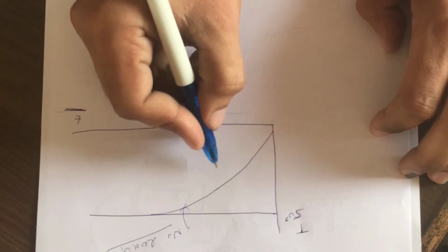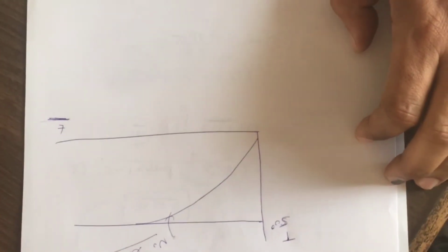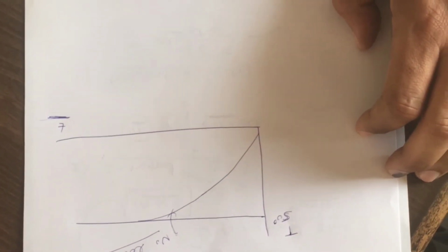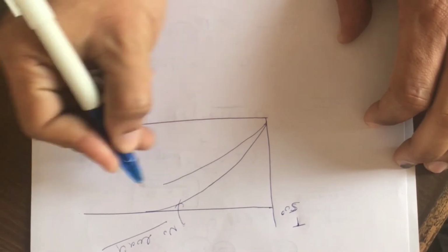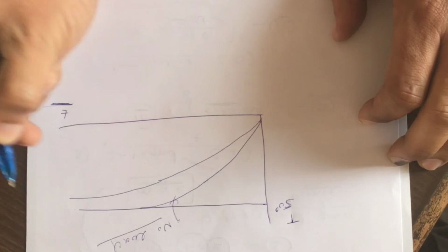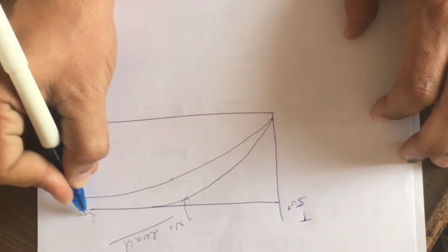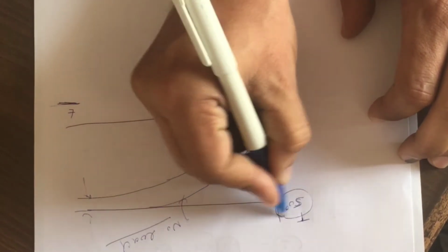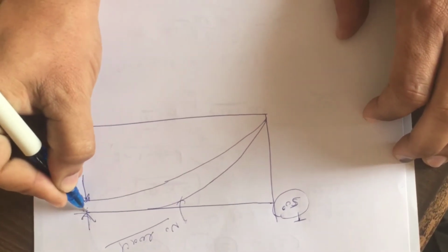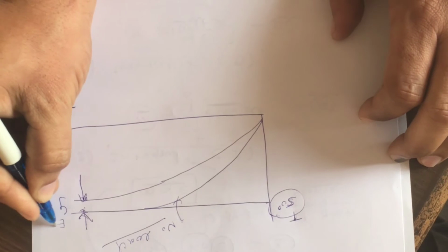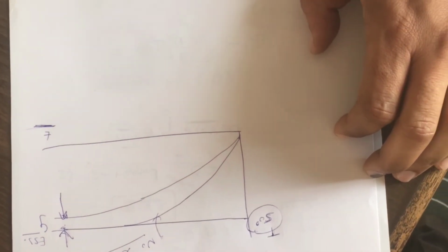And then in the second part, what we have done is we have switched on the fan, the load on the system was changed, and we observed that the temperature was never reaching the final value of 50 degrees. This difference was present over here, and this difference is known as steady state error. So what is the limitation of proportional action?